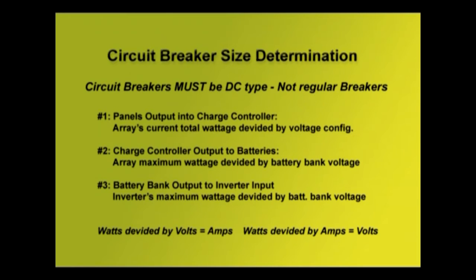And then the big one, number 3, the battery bank's output going to the inverter input. That's where our big load circuit breaker goes that provides power to the rest of the house and everything else. So that's the inverter's maximum wattage, whatever that is, divided by the battery bank voltage. And that's going to give the maximum amount of current draw. Of course, it's not 100% efficient, so it may draw a little bit more than that, but that's why we give it the elbow room.